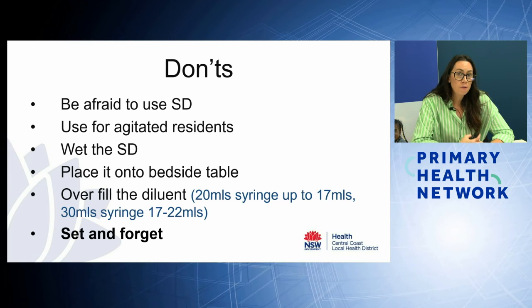Also, not overfilling the syringe. As I mentioned before, the syringes are only calibrated to a certain amount of volume. So in a 20 ml syringe, you can't run any more than 17 mls within it because the calibration fails. And if you have a pump that's been calibrated to a 30 ml syringe, they can't be run over 22 mls. That's the maximum volume that they can manage.